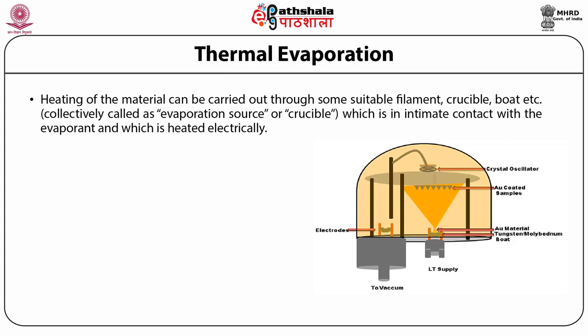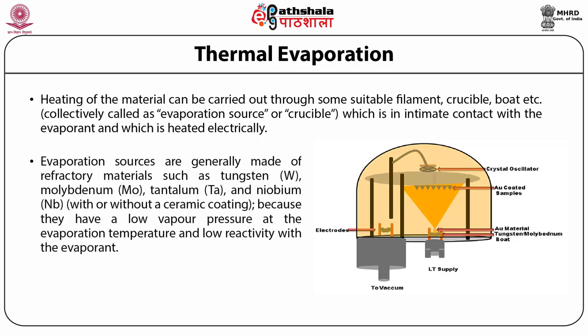Heating of the material can be carried out through some suitable filament, crucible, boat, etc., which are collectively called as evaporation sources, and are in intimate contact with the evaporant and heated electrically. Evaporation sources are generally made of refractory materials such as tungsten, molybdenum, tantalum, and niobium because they have a low vapor pressure at the evaporation temperature and low reactivity with the evaporant.